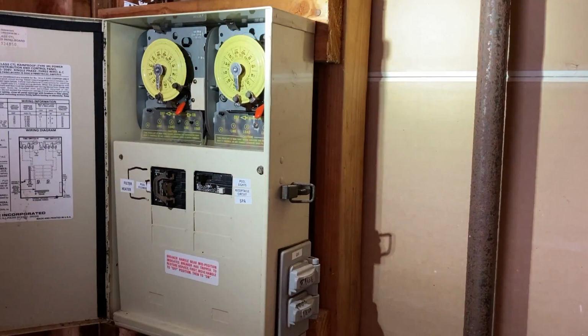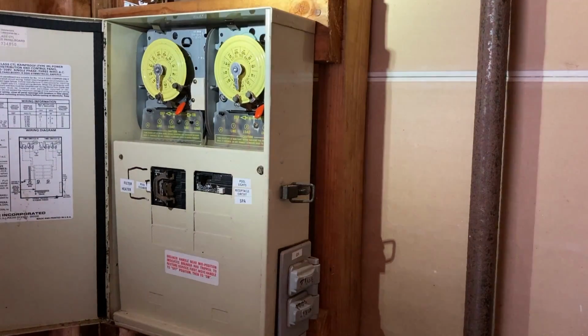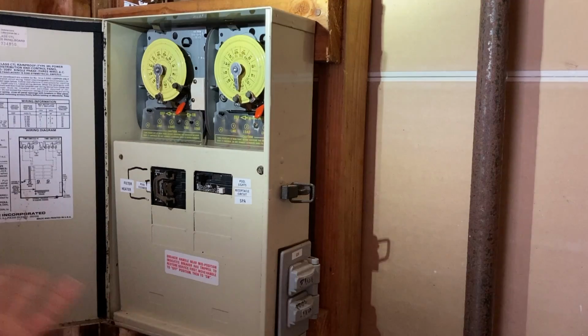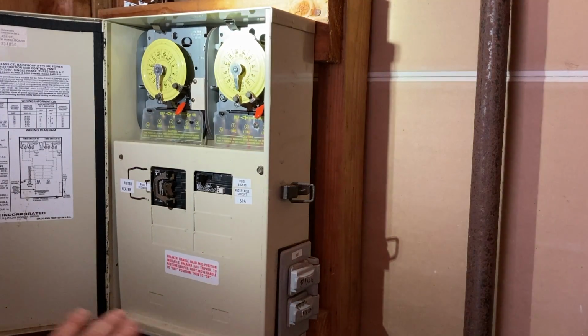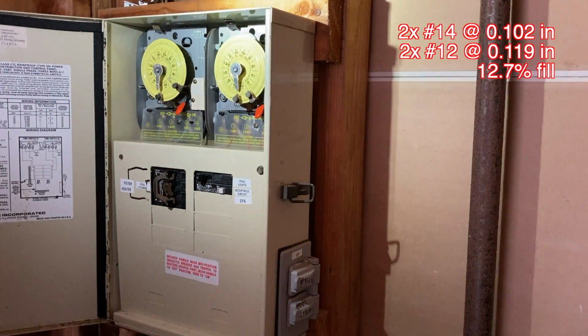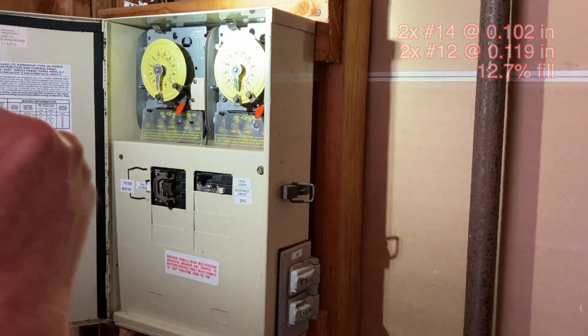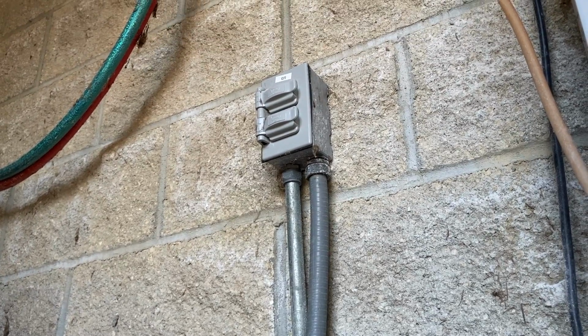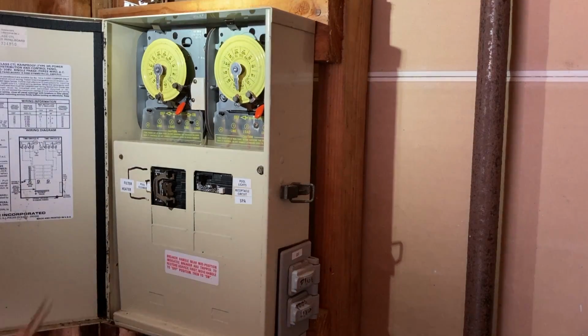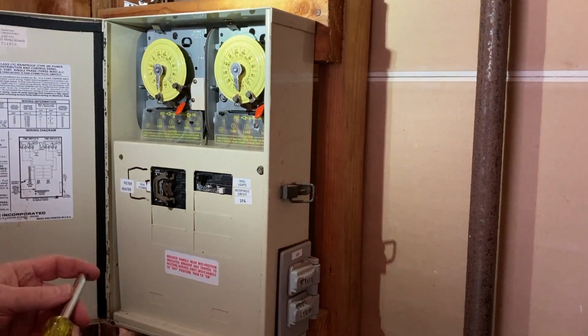Which means that it needs to be on a 20 amp circuit. And we're also going to be running the wires that feed the pump through conduit. And we're okay for conduit fill and derating. I've done the math. Not only are the wires to the pool pump going through the conduit, but there's also wires for the general purpose plug that the whip comes down from in there as well. But we're okay on heat as far as that is concerned.